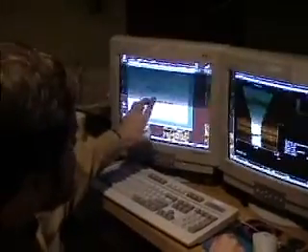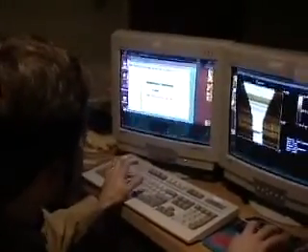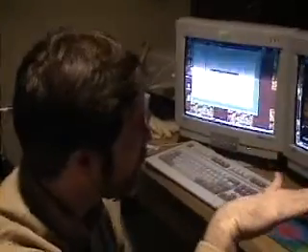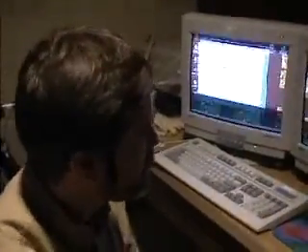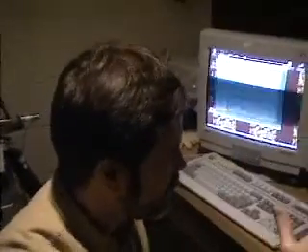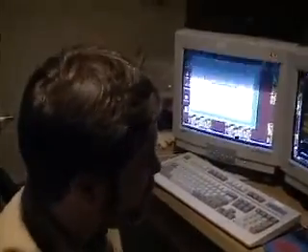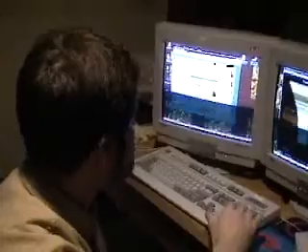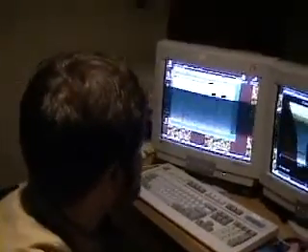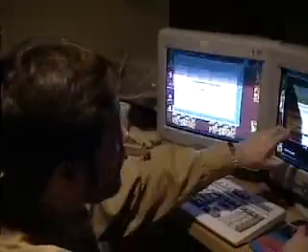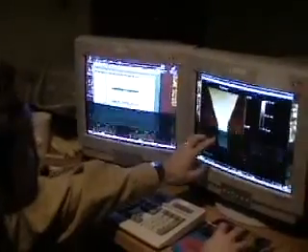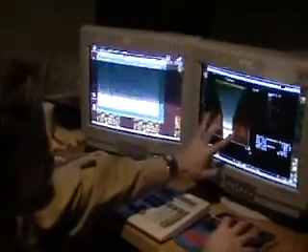The flatten order, ordinarily you want to make sure that that's set to 1, so that it will do a linear fit line by line. There are some exotic circumstances in which you'd rather fit the best fit parabola to each line or the best third order polynomial, so you can type in other things, but most of the time that should be kept at 1.